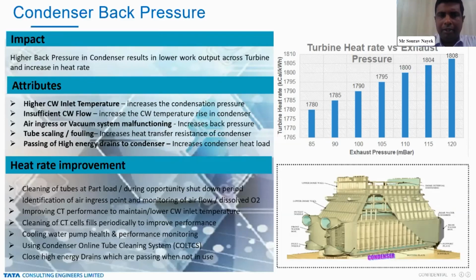And the last one is, we know that from the top HP heater and low pressure heater, the drains come to the condenser, and it all comes based on automated control loops. Now, if the passing of high energy drains happens more from the line drains or from any other drains which are not contributing to the overall cycle, then the condenser heat load will also increase and this will increase the condenser back pressure.